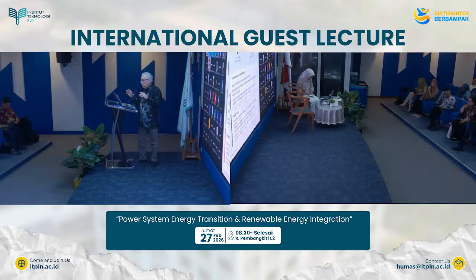What you need to imagine is that coal retirement is not just an economic problem, or a requirement to meet emission standards, or to introduce more renewable energy because of a limited resource base. It's also because you have to calculate it properly so that you don't lose stability and the operating point by losing inertia. So you've got to introduce ways to either increase it or manage operating with low inertia systems.